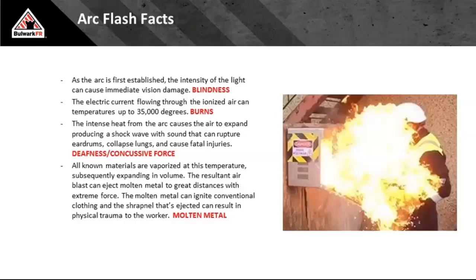The thermal energy, the blinding white light, all that stuff is bad. But you also get a bunch of other bad stuff. When you superheat air that rapidly, when you go from ambient air temperature of 70 degrees to, say, 10,000 in a blink of an eye, you have literally created a bomb. You get acoustic energy when that bomb goes off, about 165 decibels of acoustic energy in a Category 2 or 8 calorie or less arc flash. To give you some perspective, a 737 leaving the tarmac is about 135 decibels, so it's really, really loud. You get temporary deafness. You're temporarily blind from the initial flash, the blinding white light.